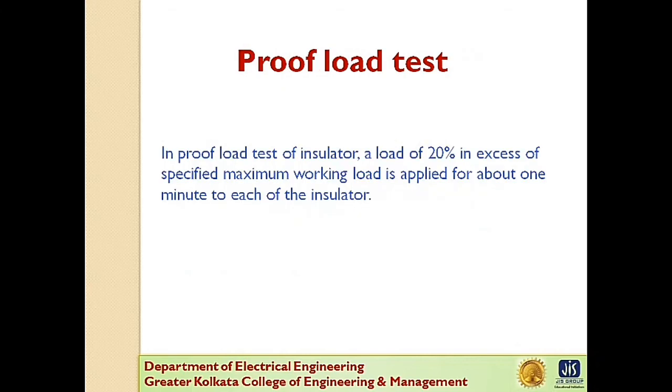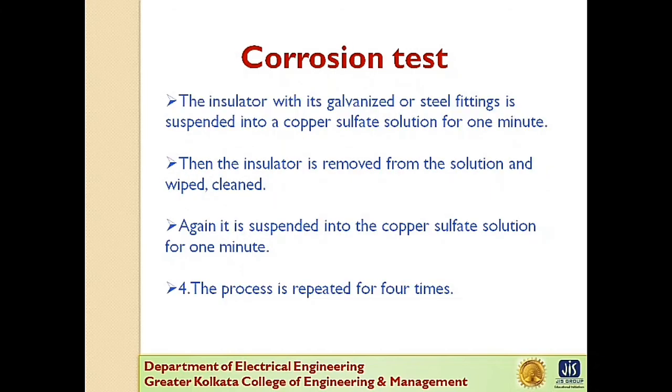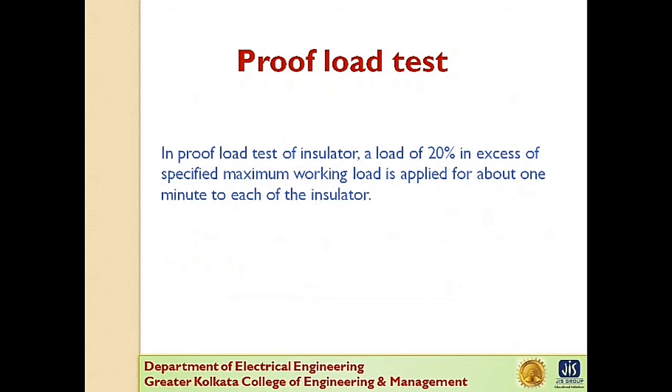Next one is proof load test. In this test, each insulator is applied with 20% in excess of working mechanical load, say the tensile load, for 1 minute. The insulator should remain undamaged after this test.